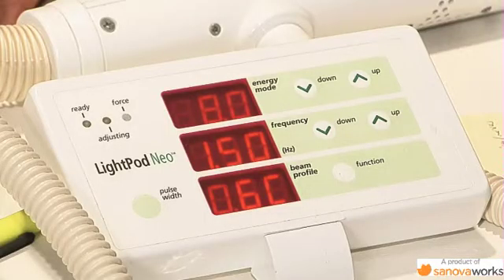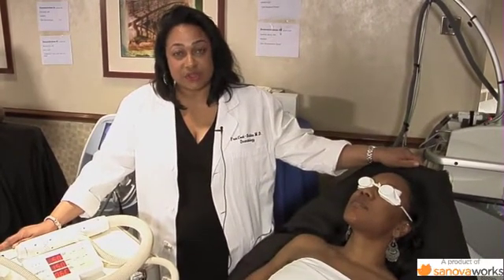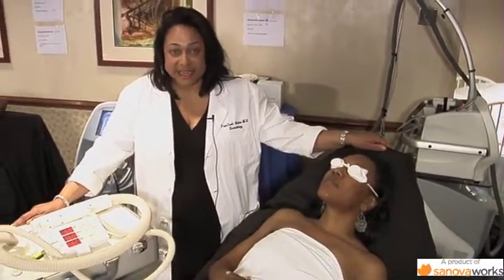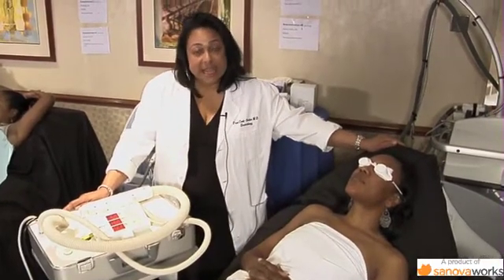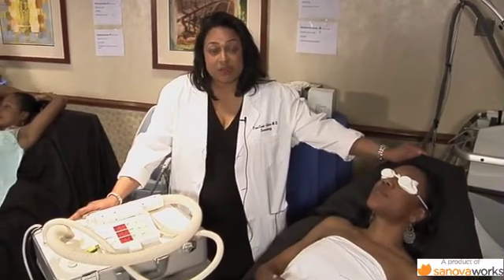Today I'm going to demonstrate the LightPod Neo laser by Aerolase. The unique feature of this technology — you've heard a lot about hair removal lasers. Dr. Battle talked about the pulse durations earlier. The traditional ND 1064 laser operates in a pulse duration between 3 and 30 milliseconds. This pulse duration is significantly reduced — it operates at 0.65 milliseconds, which is significantly less than traditional lasers.